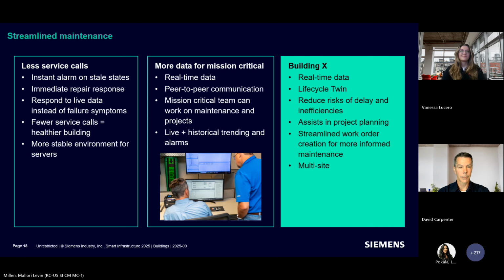Some of the maintenance options that have come from this newer infrastructure: when they get an alarm, it's an actual alarm. With the MSTP network, the older system based on an N2 communication protocol had problems—there were many layers to get data from the controller through hubs and up into a front end, leaving a lot of chances for false alarms.